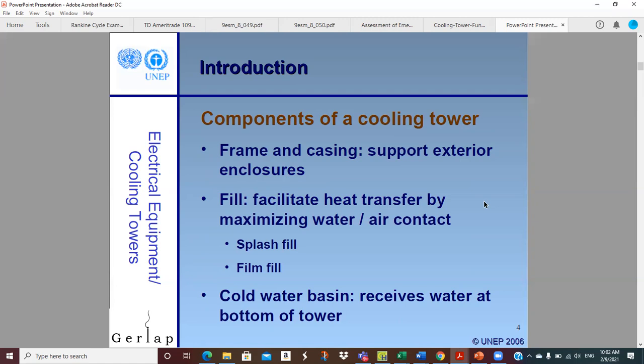And then, of course, we've got the cold water basin, which receives water at the bottom of the tower. That's where the blowdown comes out of. It's where the makeup water goes into.